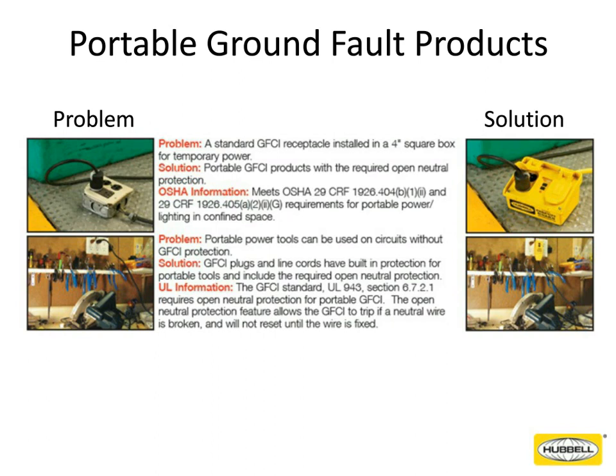So a portable ground fault must have what we call an open neutral relay. And basically what that does for you is, if you have an extension cord running across the facility, a tow motor drives over it, and the neutral cord gets severed, you still have power coming in on that line. You don't have a circuit closed, so you don't have power to your equipment, but you do still have power on that line, and you can still become the ground fault mechanism. You can still get shocked even though there is no circuit and that piece of equipment isn't operating.